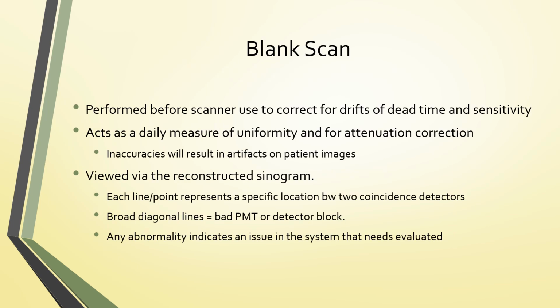So the blank scan has to be performed before a scanner use for the day to correct for drifts of dead time and sensitivity. It acts as a daily measure of uniformity and for attenuation correction. Inaccuracies in the blank scan, though, will result in artifacts on the patient images. This is viewed via a reconstructed sinogram. Each line or point represents a specific location between two coincidence detectors.